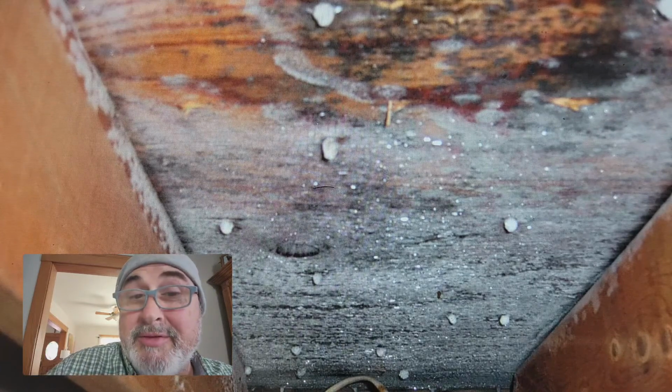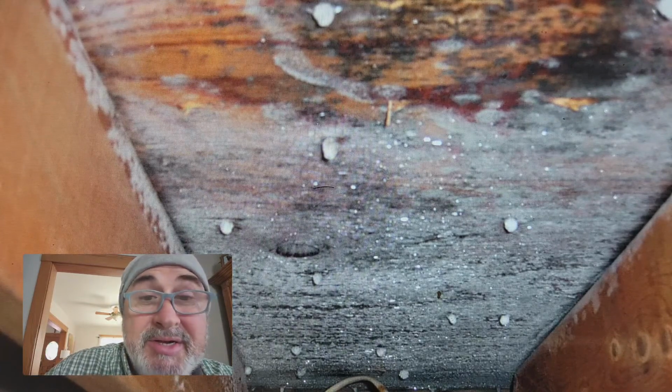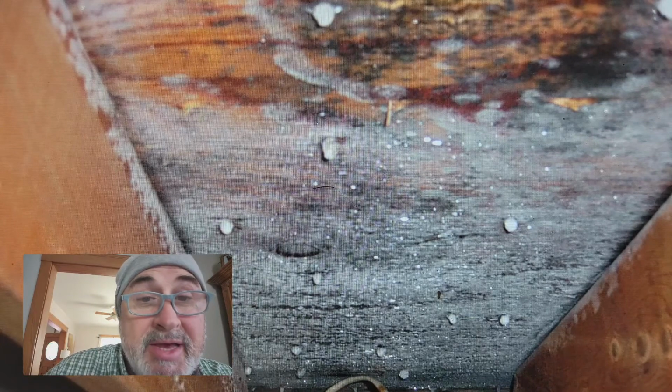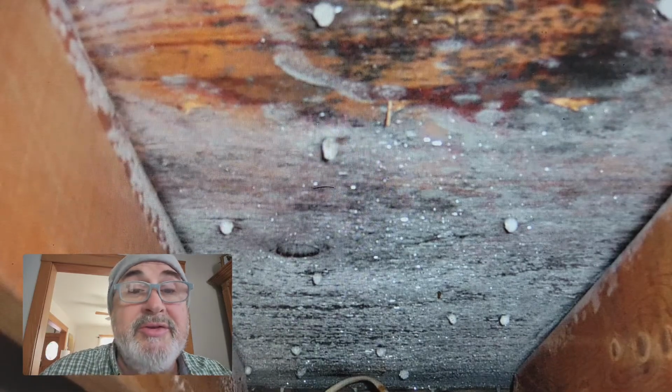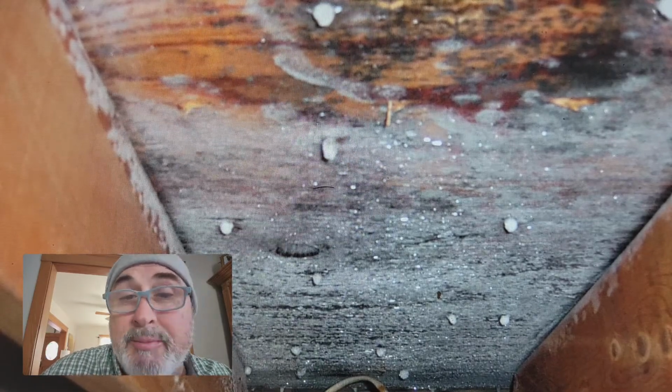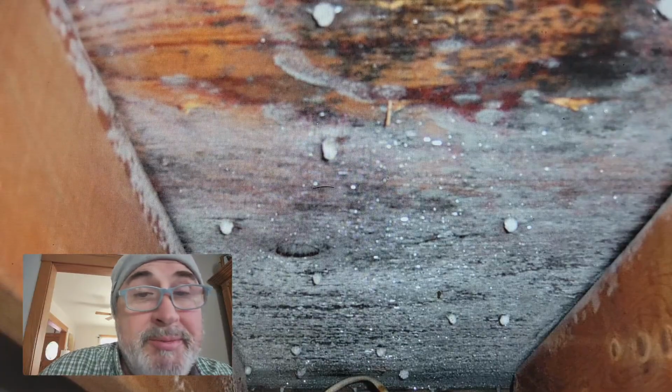And of course you have to have a thermal bypass, so the attic access isn't sealed, insulated, weather stripped. The door to the attic needs to be insulated and weather stripped because you don't want the air to go up there, and an unbalanced heating system. So if you got negative pressure in the basement because of duct leakage, and you got positive pressure upstairs, bada bing, you got moisture, you got positive pressure, you're blowing up your attic with moist air.